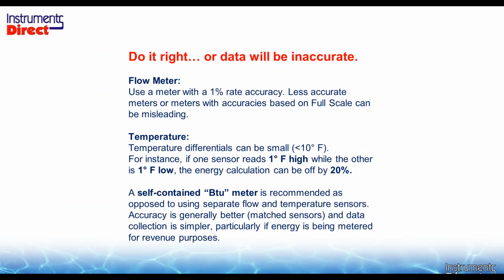Step one, you need to have a flow meter that's accurate. If you don't have an accurate flow meter, you have inaccurate data. So my recommendation when you're using an ultrasonic flow meter is to get something that's 1% of rate, and some of the meters we put on the screen there will meet that requirement. Well, there are a lot of meters out there that cost far less that will not meet that requirement. So you need an accurate flow meter of rate. Some of the insertion paddle wheel flow meters of yore that have been around for a long time, industry standard, have accuracies of full scale. You can be a couple percent off very easily just by using a brand new calibrated full scale paddle wheel flow meter versus an of rate meter. It's not doing anything wrong. People don't understand the differences between the two.